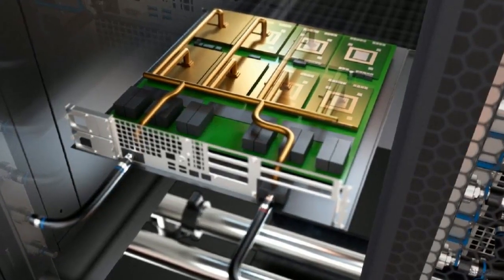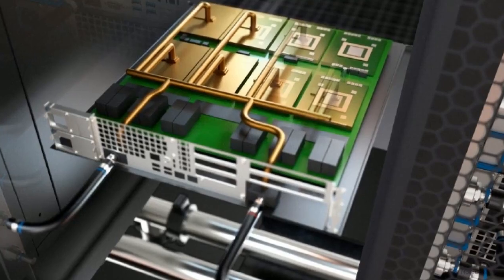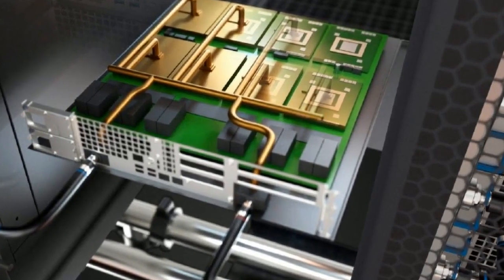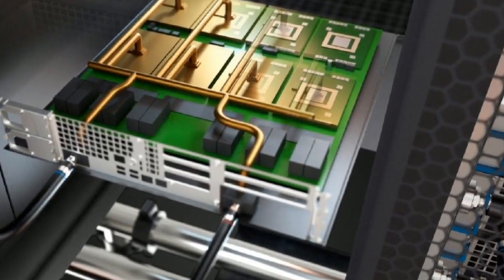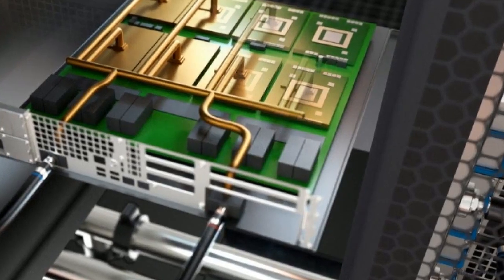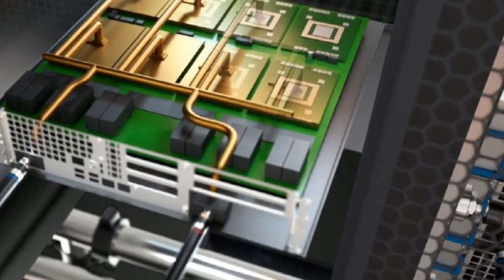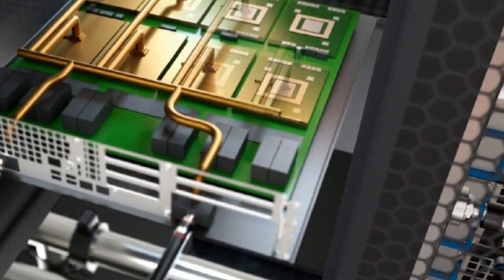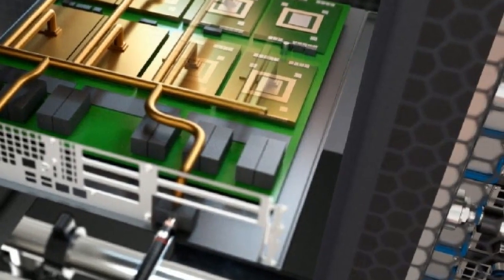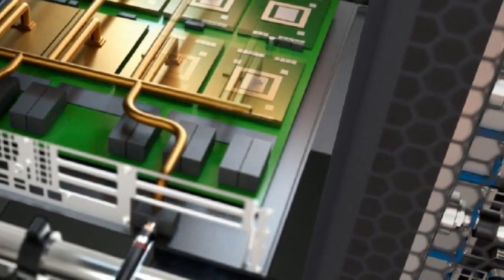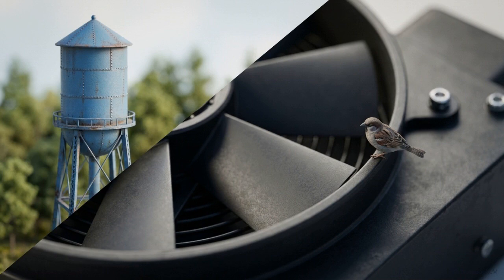Alternatively, facilities deploy direct-to-chip cooling. Sealed copper pipes run liquid directly to the microprocessors, targeting the hottest components. Because the fluid is in a closed loop, there are no evaporative water losses. This removes the need for rooftop cooling towers and high-velocity fans. By changing how heat is managed at the processor level, the facility stops draining municipal aquifers and silences the industrial drone.